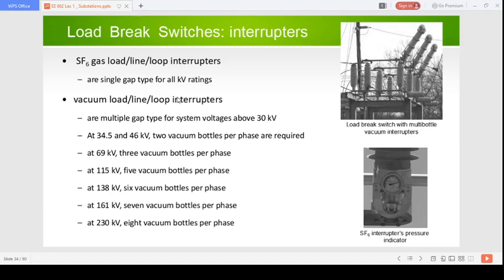So vacuum interrupters come with different arrangements for different voltages. They are multiple gap type for system voltage above 30 kV. So if the system voltage is greater than 30 kV, you can use multiple gap type systems. Here you can see a load break switch with multi-bottle vacuum interrupters. You can see there are a number of vacuum bottles, 1, 2, 3, which handle the interruption.